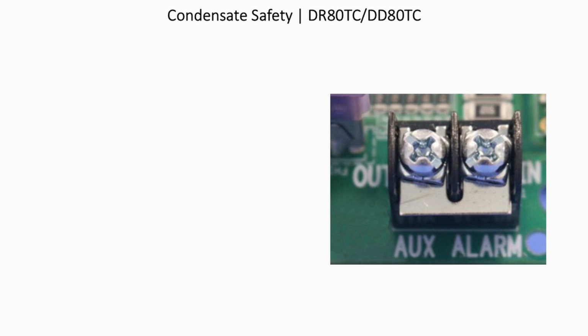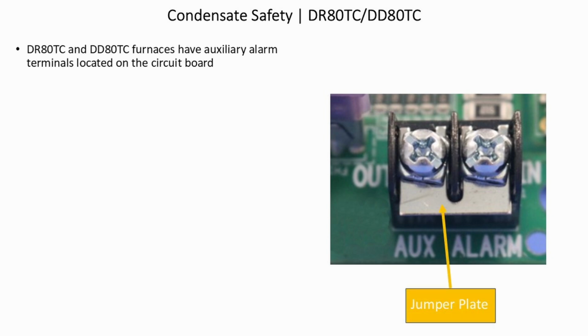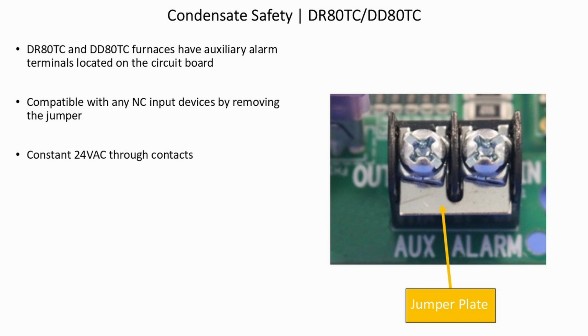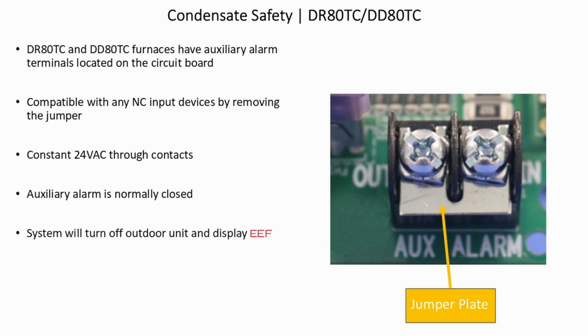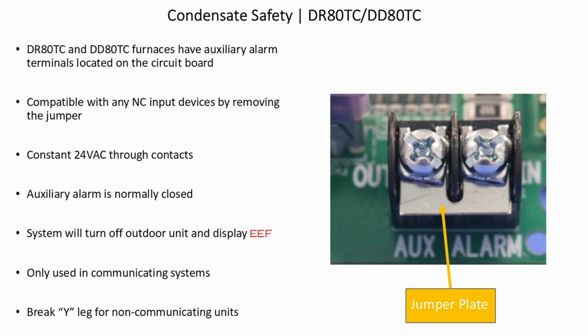Condensate safety. The DR80TC and the DD80TC furnaces have auxiliary alarm terminals located on the circuit board. Compatible with any NC, normally closed, input device by removing the jumper. Constant 24-volt AC through the contacts. Auxiliary alarm is normally closed. System will turn off the outdoor unit and display EEF. Only used in a communicating system. Break the Y wire for non-communicating units.